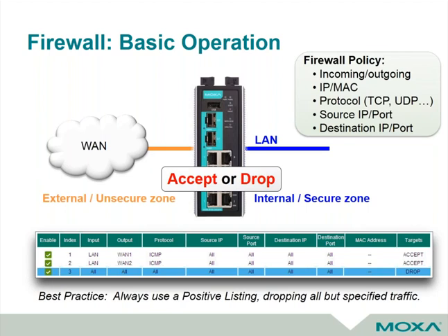I probably should have highlighted that. That basically says deny everything else. And then on top of that, these items have a higher priority. You say, I want to accept that traffic. So I just realized this one's maybe not the best example. It's using ICMP, which is the protocol for ping. But let's say that was port 502 for Modbus TCP, and you wanted to allow a Modbus TCP request to come into this site. This is where you can control that.